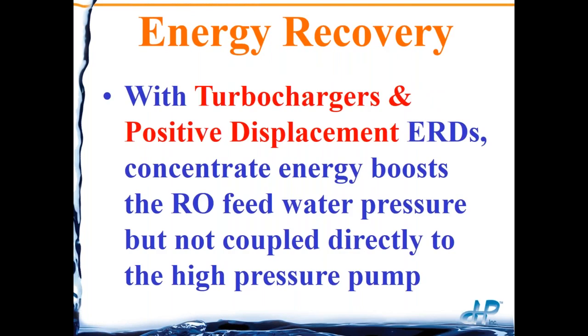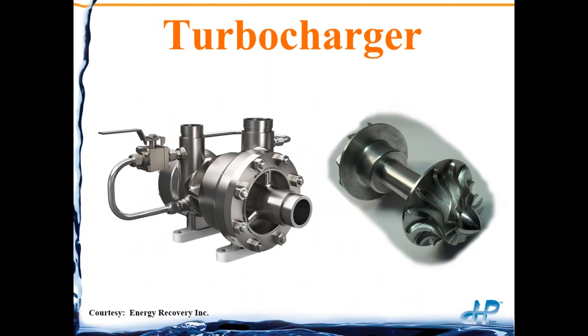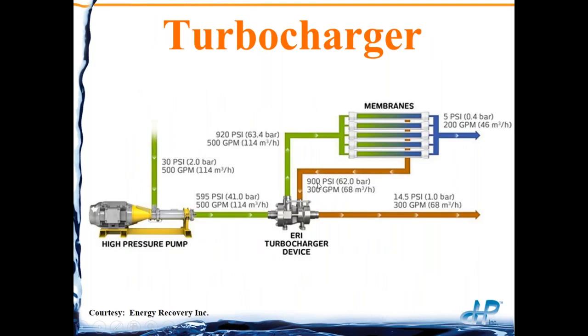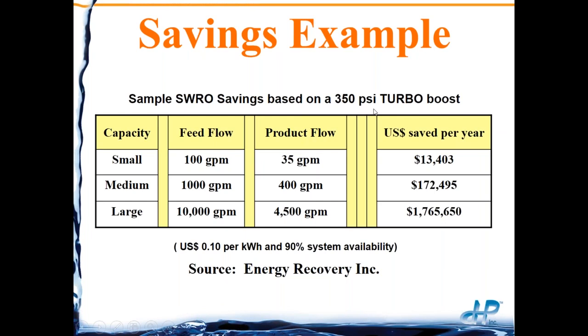With turbochargers and positive displacement, the energy recovery devices take the concentrate energy to boost the RO feed water pressure, but they're not coupled directly to the high pressure pump. With the turbocharger, you have a dual pump that has two impellers on the same shaft. The concentrate is coming and turning the impeller on the concentrate side, which — since it's connected to the impeller of the feed water — is boosting the pressure to the RO system. Here's an example at 10 cents per kilowatt hour showing what you might save with small, medium, and large systems.